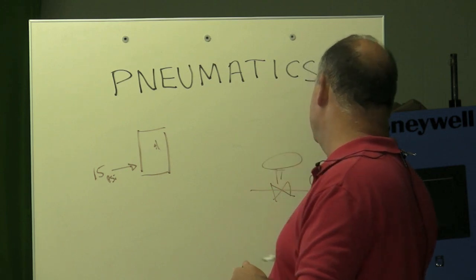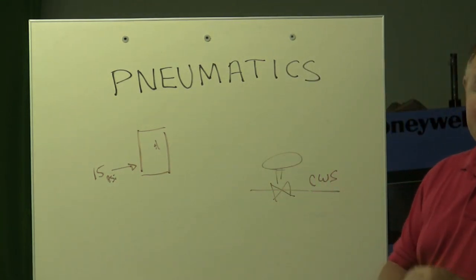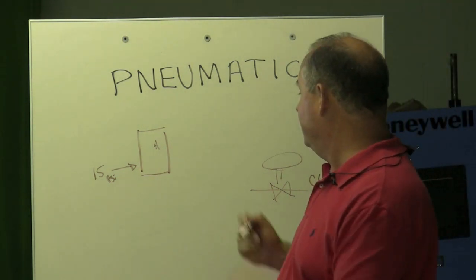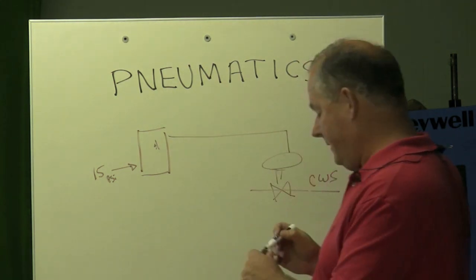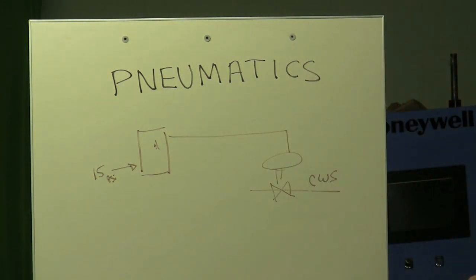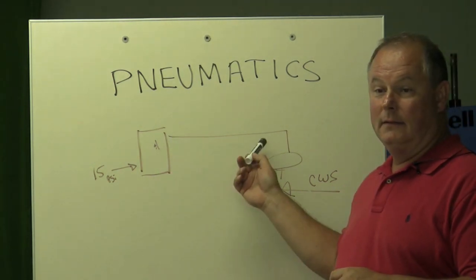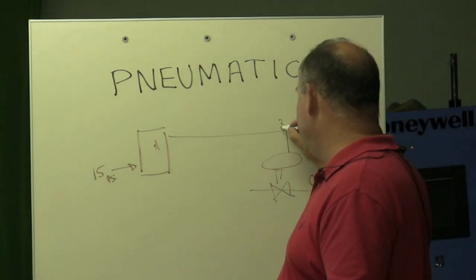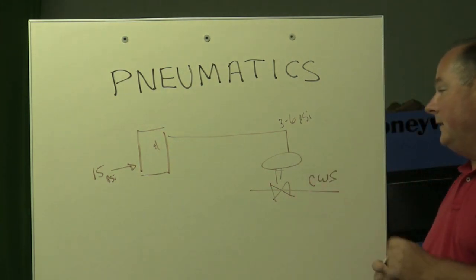We're going to have some kind of actuator over here with some kind of spring range. We'll choose the spring range based on whether it's normally open or normally closed. We don't really care what it is for this application. There's our thermostat and here's our branch line that comes over.